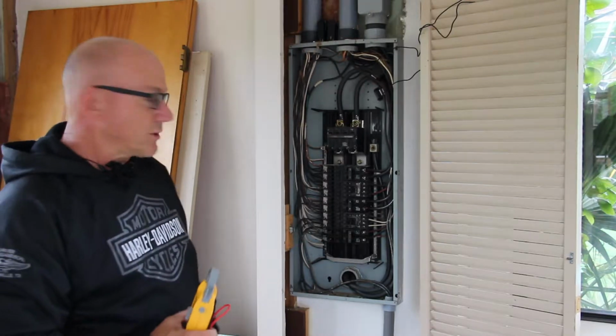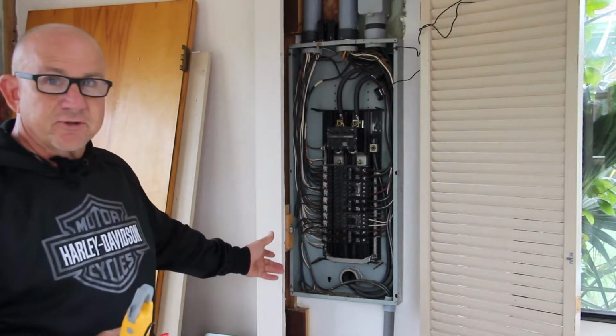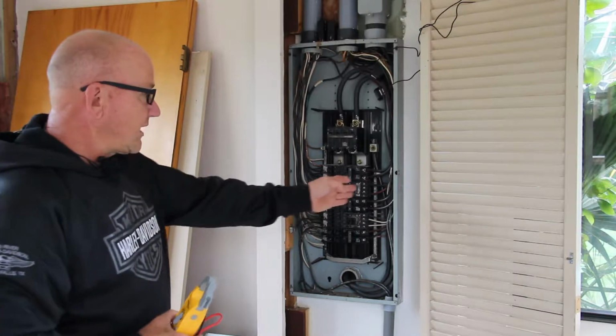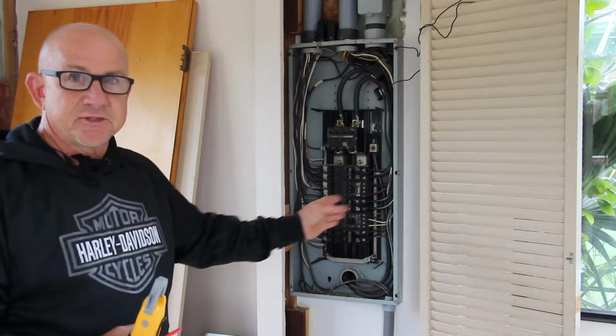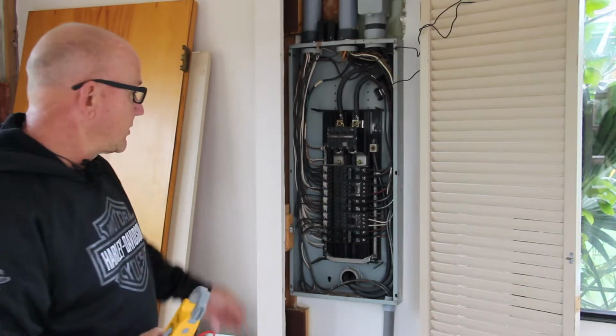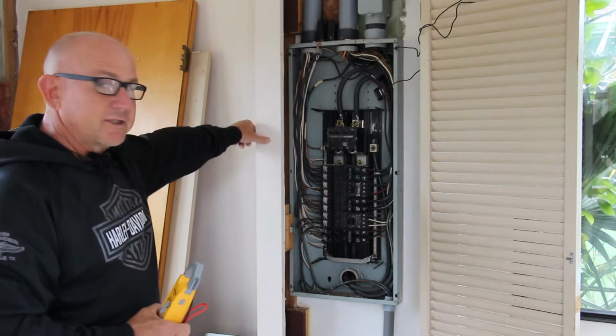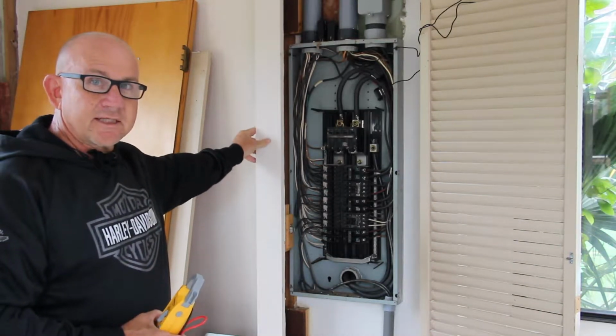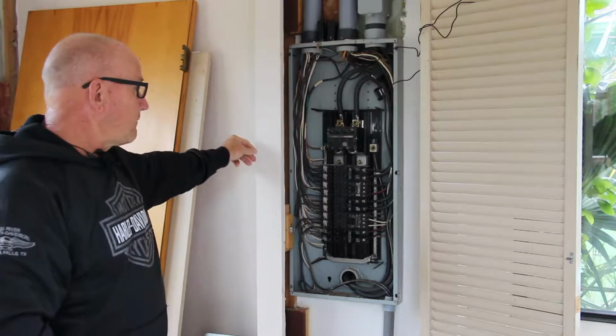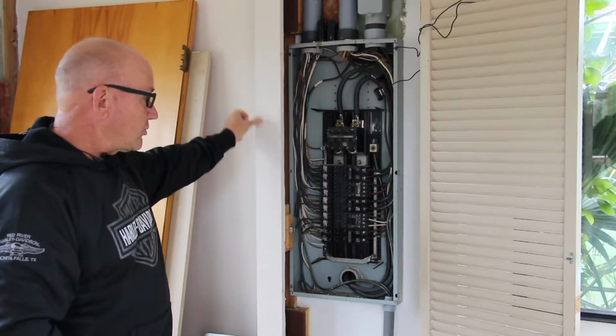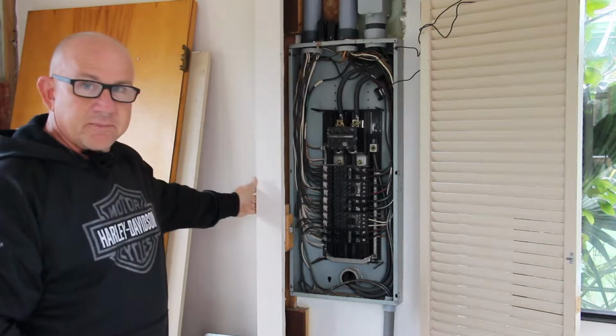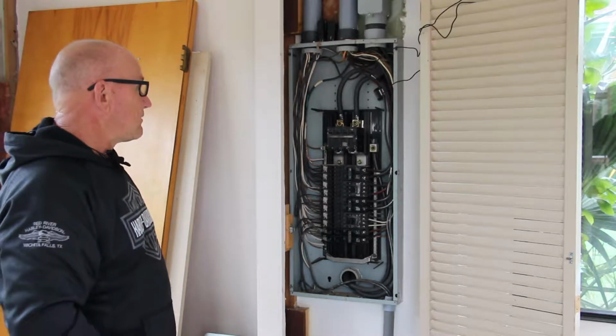One of the first things we're going to be looking at is clearances to electrical panels. You're supposed to have approximately 18 inches on each side and 3 feet in front. We can see here that this panel is restricted, does not have clear access for proper servicing because of the enclosure that it's around. That's going to be a problem. We're going to write that up first off.